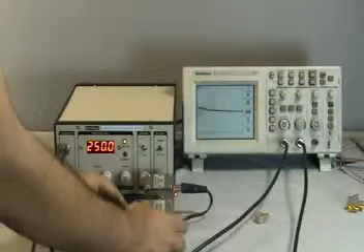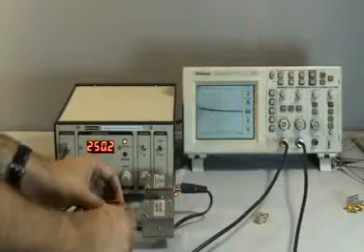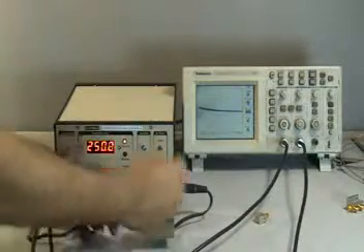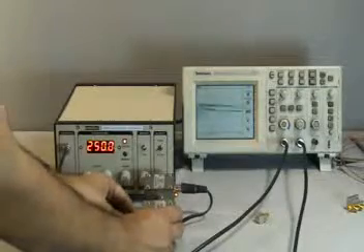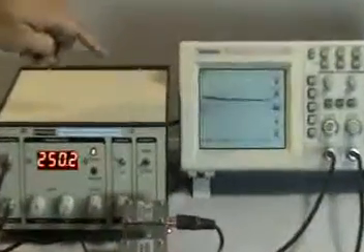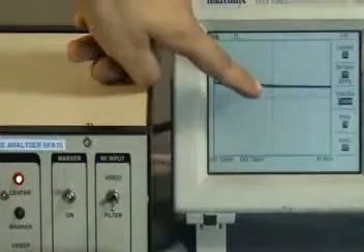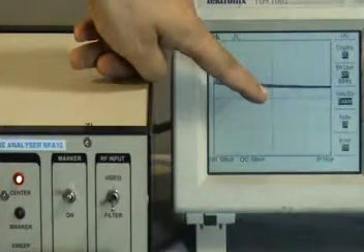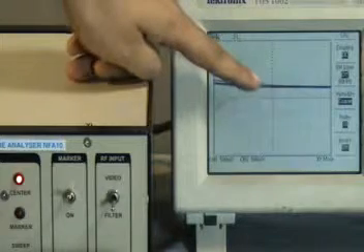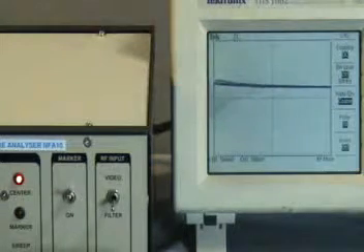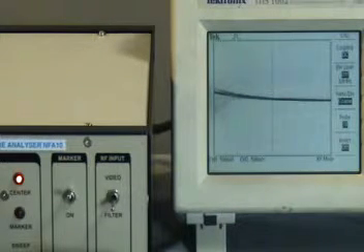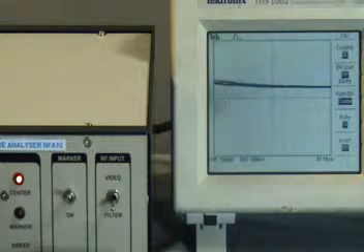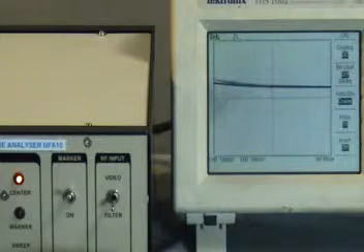Now the moment we switch on the excess noise generator, 12 dB of excess noise above the thermal noise will be applied to the preamplifier. And we observe that the signal level has risen by approximately 0.9 graticules. Let me show it to you again, and observe it carefully. This is right now at the center of the display, and now the signal has increased by about 0.9 graticules.